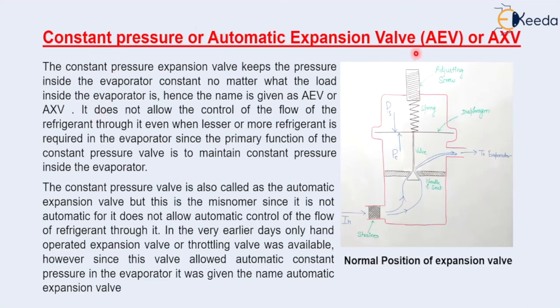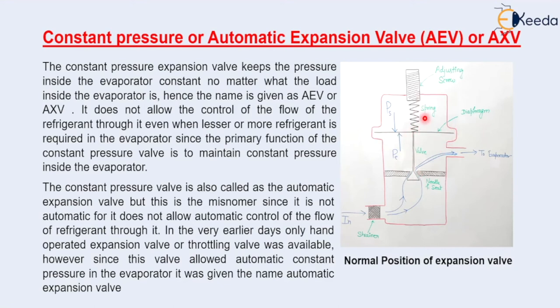Now let's see the constant pressure or automatic expansion valve, also called AXV. In the automatic expansion valve, the arrangement includes a strainer at the inlet through which refrigerant enters and flows to the evaporator. The strainer removes foreign particles and dust. The valve assembly consists of a needle and seat valve, a diaphragm, a spring, and an adjusting screw with which the spring pressure can be adjusted.